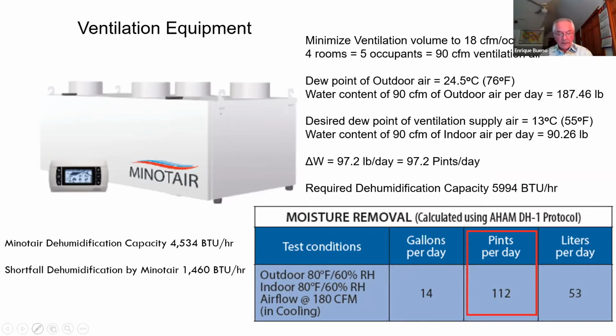And also, by increasing the design dew point of the ventilation supply air to 15.6 centigrade or 60 Fahrenheit, which is an adaptive mode that, in my opinion, will be tolerable by the local community, considering that the outdoor dew points are 24.5 and 76. So we're running dew points from 76 down to 60, so that should be okay. And a 9,000 BTU mini split will have a dehumidification capacity of 1.5 pounds per hour. So that's more or less close to 40% of what we need. So that will take care of this shortfall, as well as any internal latent loads that we may have.